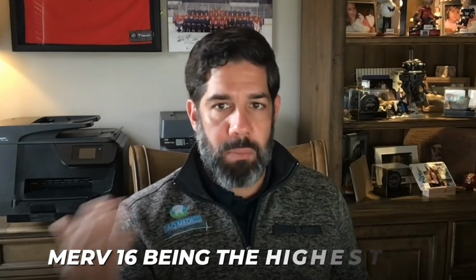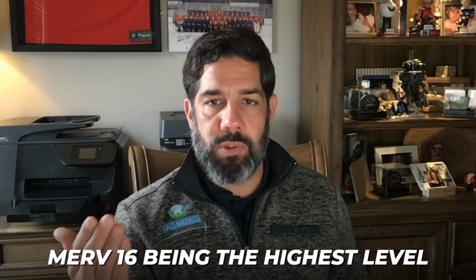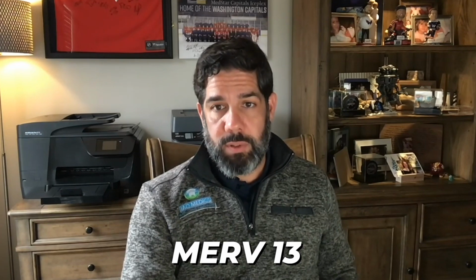Now the MERV scale, which measures filtration efficiency, tells us MERV 16 being the highest level is going to provide the most efficiency. However, you can get MERV 16 filters that are non-electronic, but you're going to have a significant restriction of airflow like you just mentioned. So one way to avoid that is by using a MERV 13 filter, and that MERV 13 filter is going to allow air to pass through sufficiently so we don't have restrictions causing equipment to ice up or limits to trip.